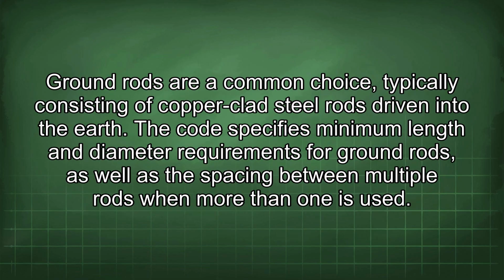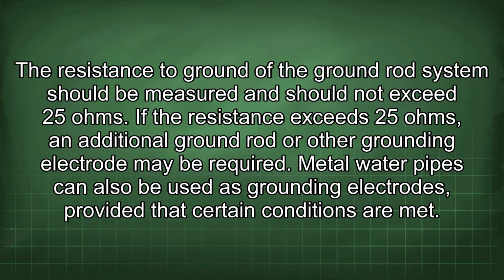Ground rods are a common choice, typically consisting of copper-clad steel rods driven into the earth. The code specifies minimum length and diameter requirements for ground rods, as well as the spacing between multiple rods when more than one is used. The resistance to ground of the ground rod system should be measured and should not exceed 25 ohms. If the resistance exceeds 25 ohms, an additional ground rod or other grounding electrode may be required.